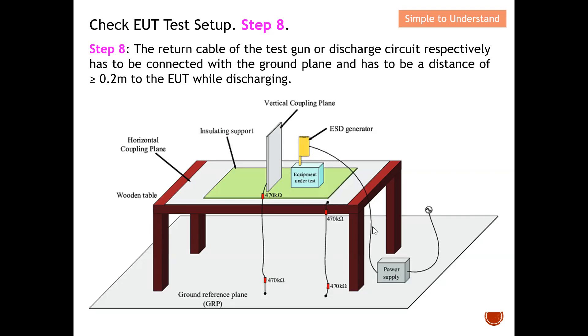Step number eight: the return cable of the test gun, or the discharge circuit, must be connected to the ground plane and must maintain a distance of at least 0.2 meters from the EUT during discharge. If this length is less than 0.2 meters, you do not comply with step number eight.